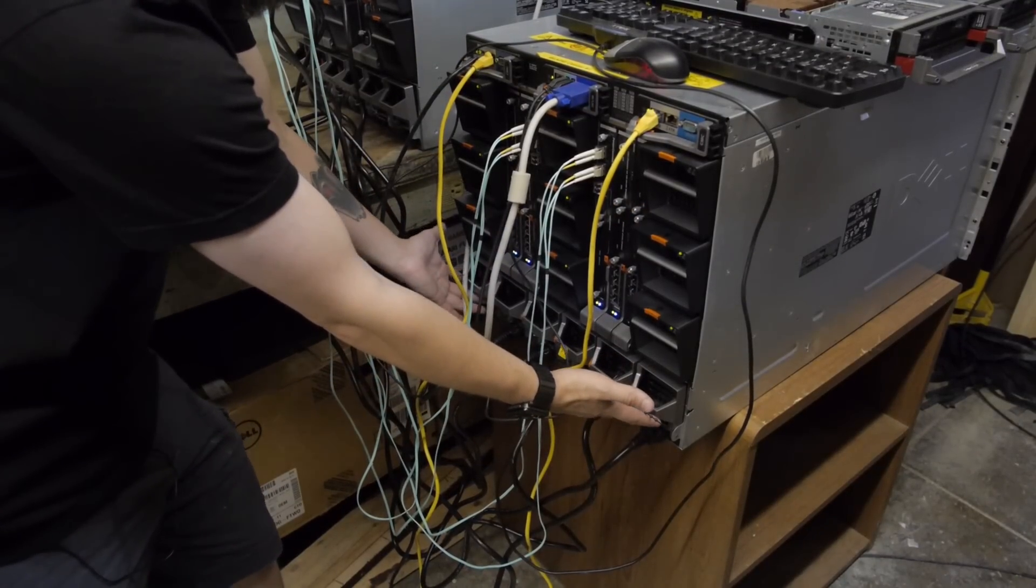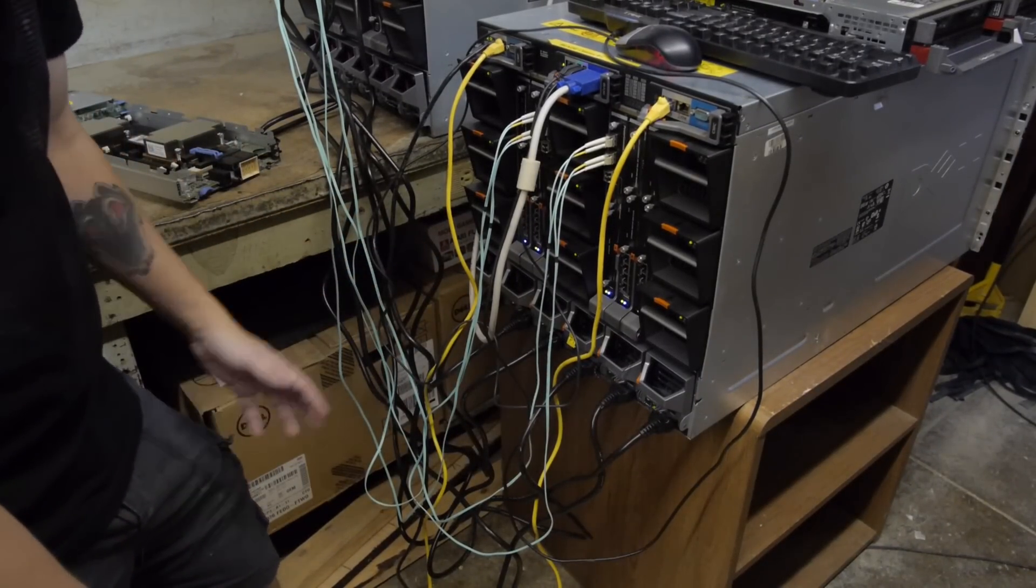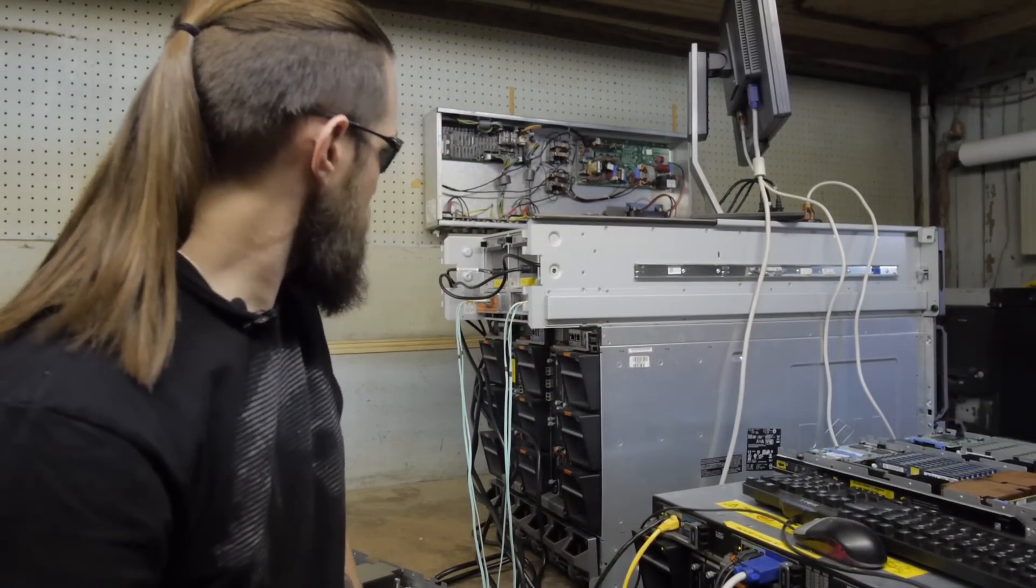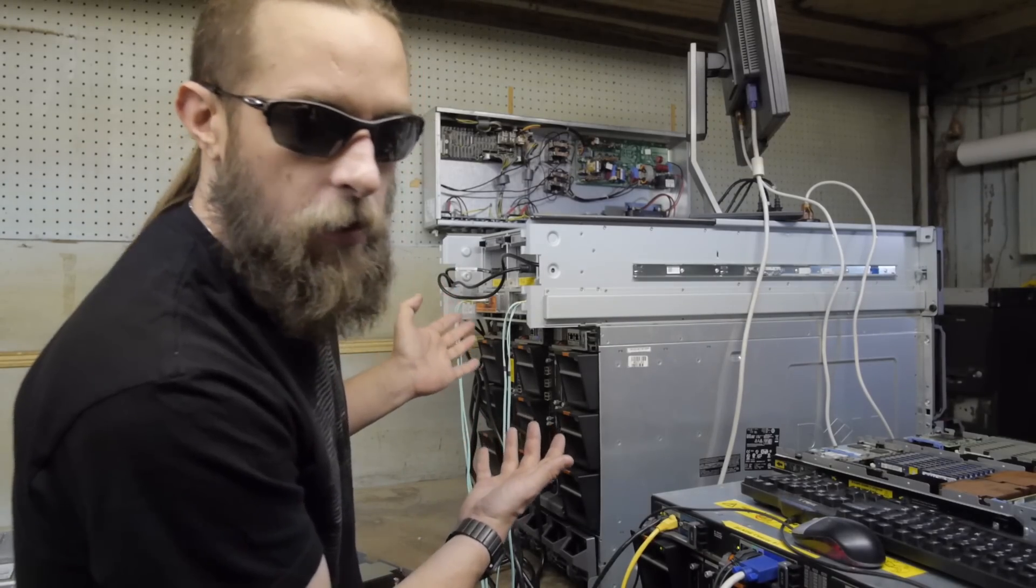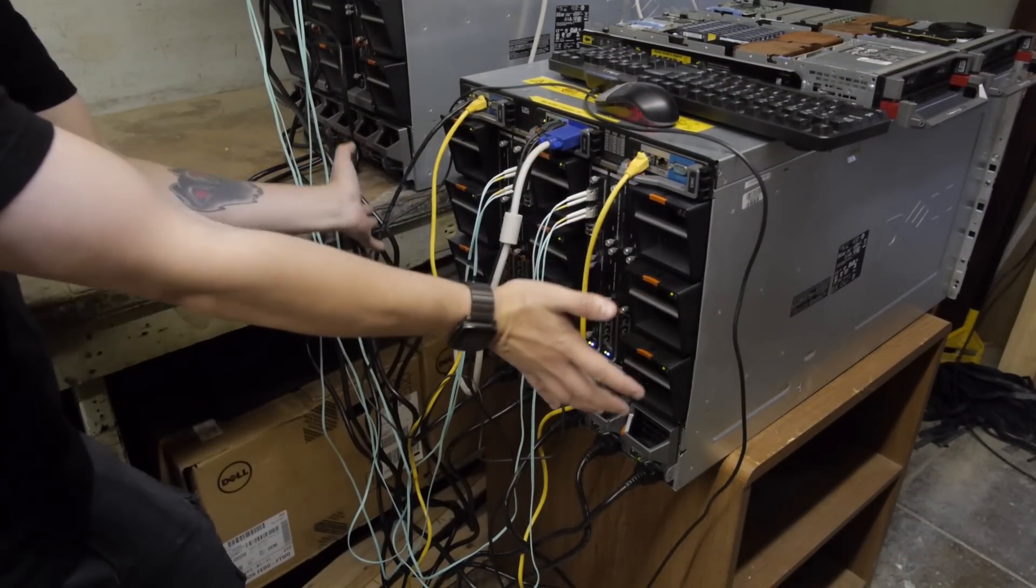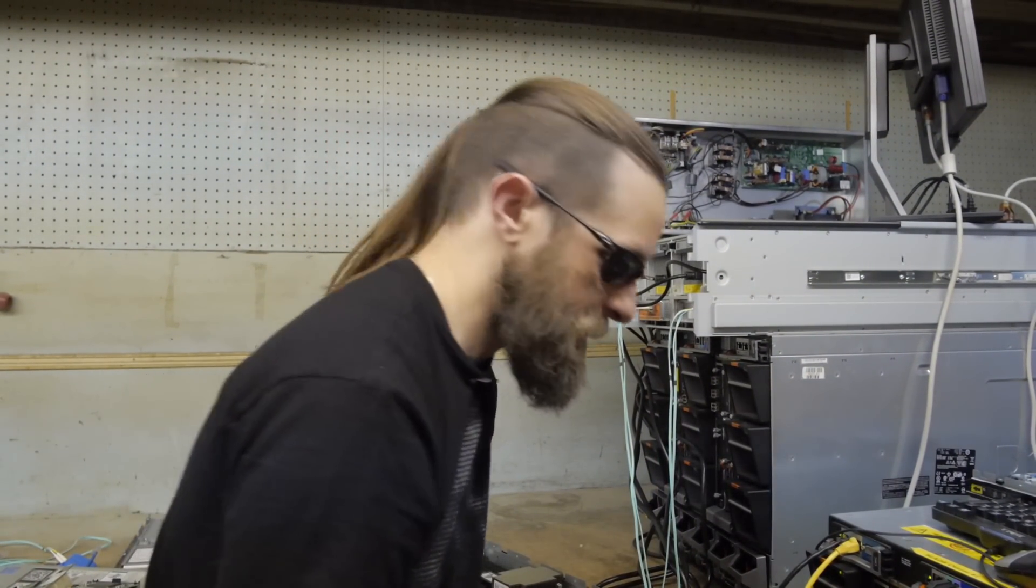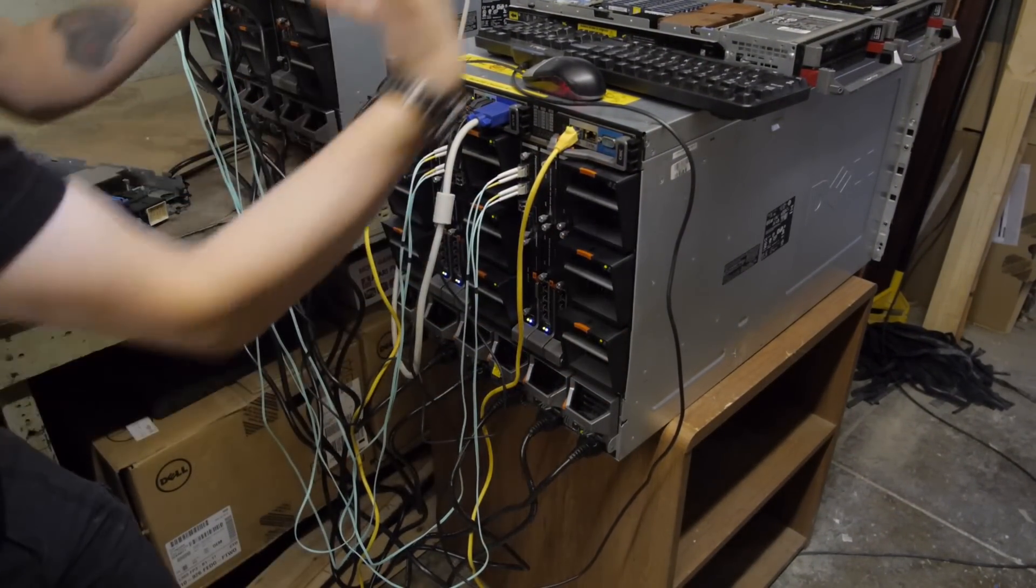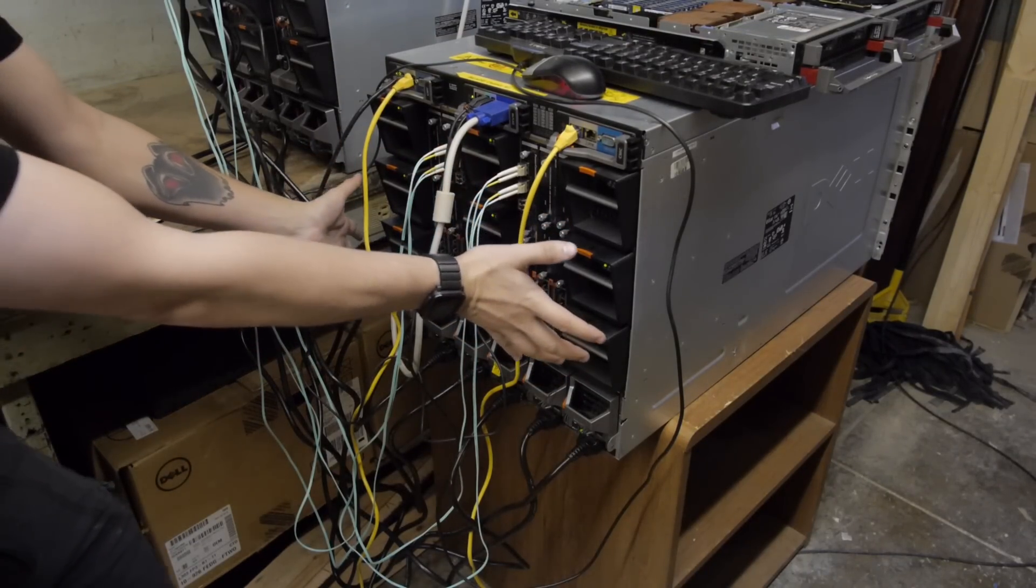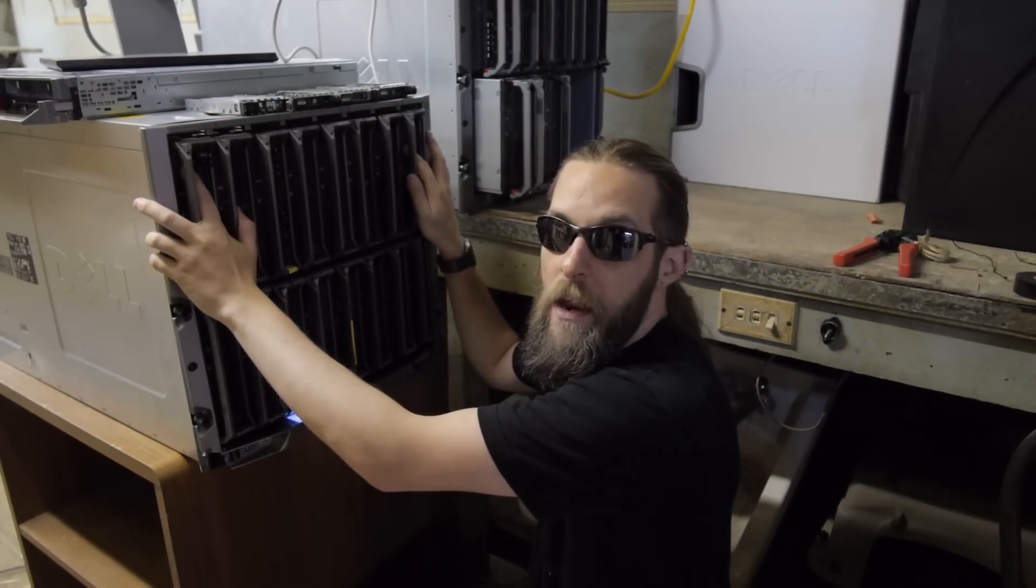You've got six power supplies. And these things are hefty and they're running on 208 volts. You've got to have a 30 amp PDU because this thing sucks a lot of juice. You can see ours back there is just eating power. It's about as much as a dryer on full blast. So you can swap your dryer off for one of these things. It's also got nine fans. These things are blowing air or pulling air through the entire system and just blasting me right now. It's actually nice and cold because there's only one blade on.